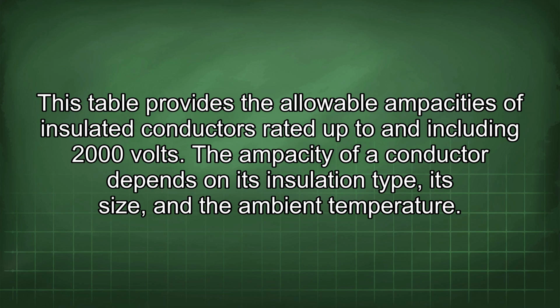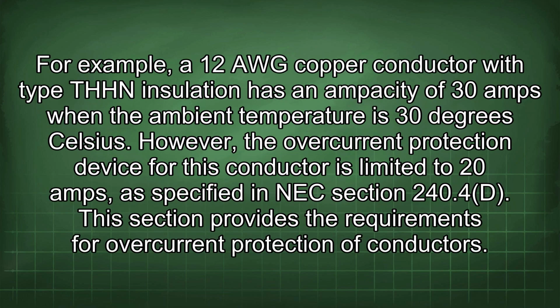The ampacity of a conductor depends on its insulation type, its size, and the ambient temperature. For example, a 12 AWG copper conductor with type THHN insulation has an ampacity of 30 amps when the ambient temperature is 30 degrees Celsius. However, the overcurrent protection device for this conductor is limited to 20 amps, as specified in NEC section 240.4(D). This section provides the requirements for overcurrent protection of conductors.